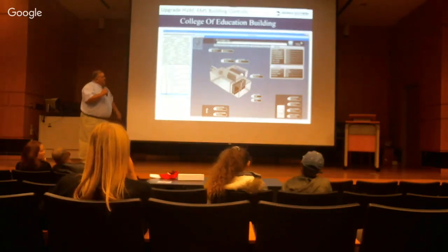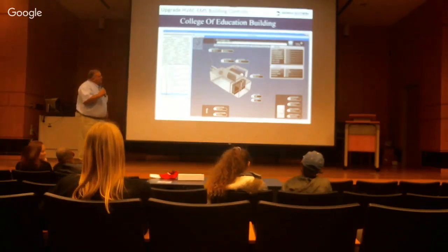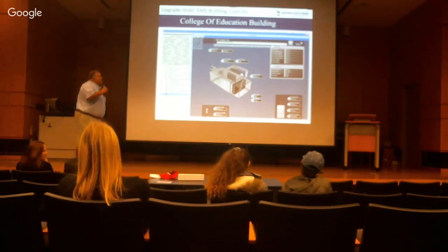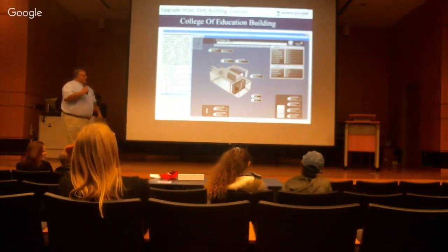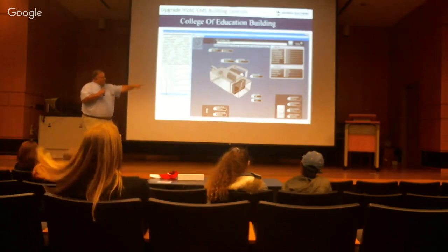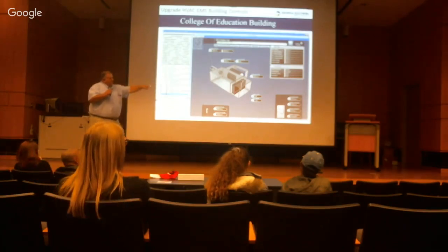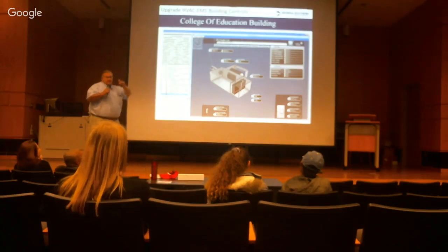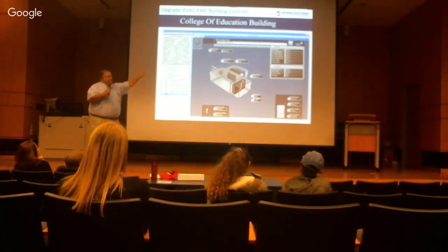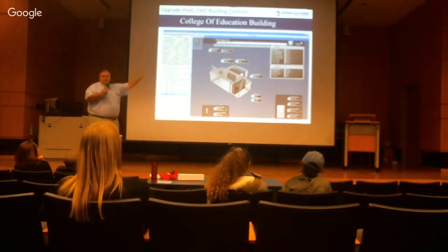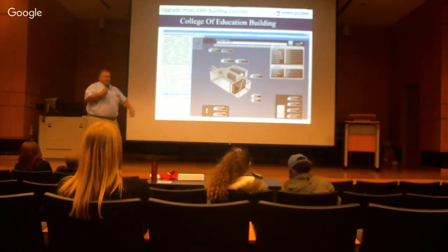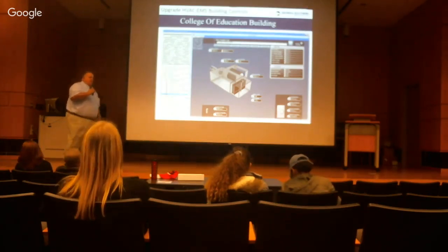What you see is occupied heating, occupied cooling, unoccupied heating, unoccupied cooling, standby cooling, and standby heating. Down here on the bottom, you see the zone temperature — they have a digital thermostat and can see all that, and so can we. They get a 5-degree movement window that they can see, but we can see more than that; they can't see the setting at the top. So we have somebody monitoring that system around the clock, 24 hours a day.